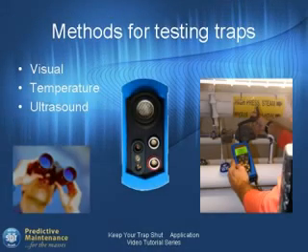Traps can be tested using one of three methods. With SDT's new SDT 270, you can do all three with one instrument at the same time: visual testing, temperature testing, and ultrasonic testing. When testing traps using these methods, it is equally important to know your surroundings and pay attention to safety. Serious burns can result from carelessness when working in and around steam systems. Know the system and understand how the traps function.